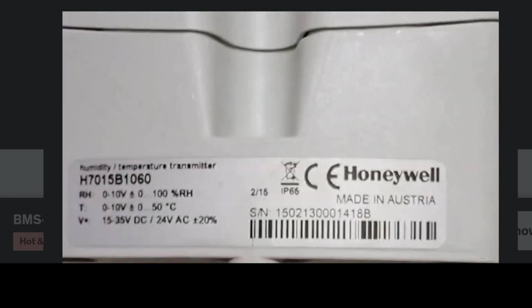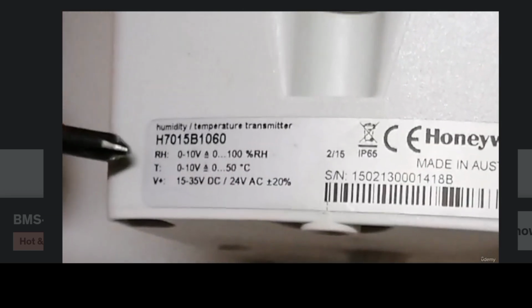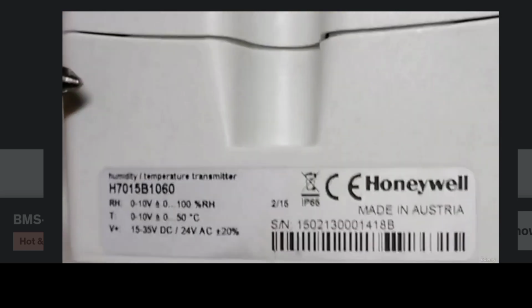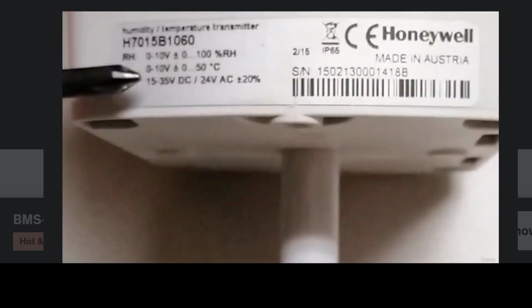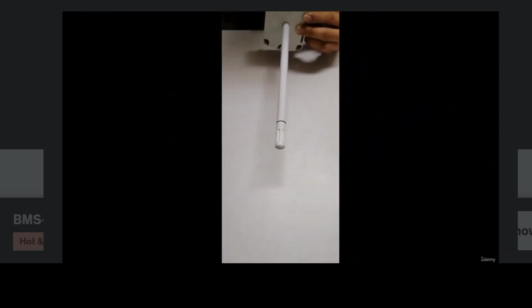Since it is a transmitter, it provides a 0 to 10 volt signal for humidity, and for the temperature we also need a 0 to 10 volt signal. We also need a power supply. We can use a 24 volt DC or 24 volt AC power supply for this transmitter.